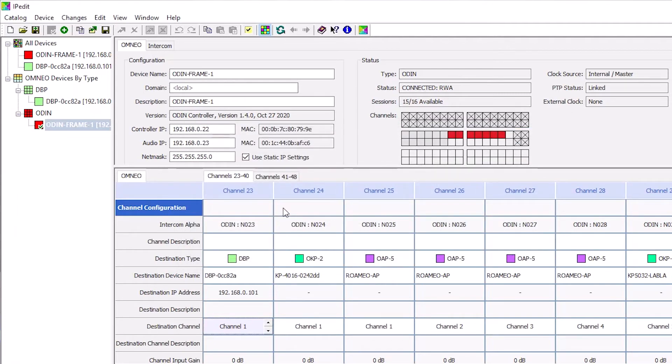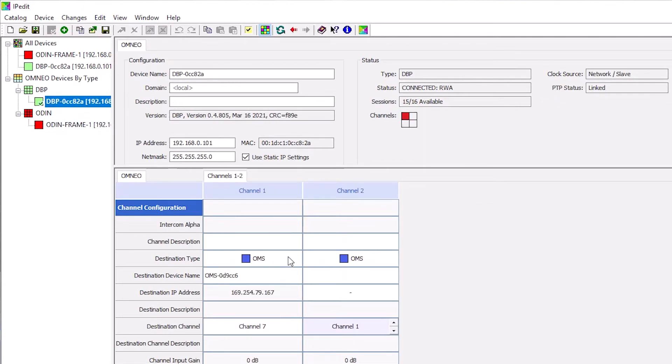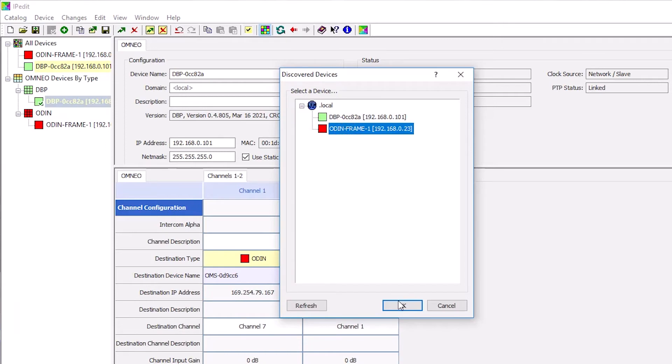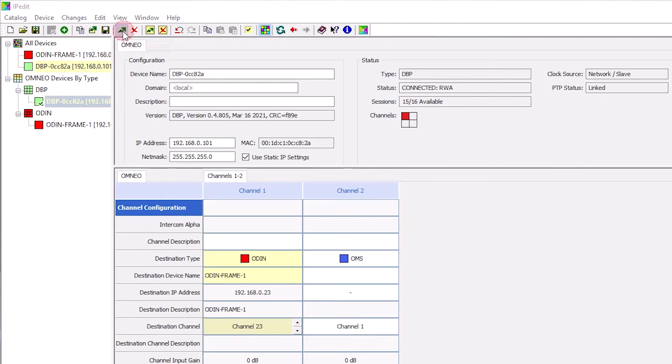Now we will configure an OMNEO channel for DBP using IP-Edit. Using the Channel Configuration pane, in the Destination Device Name field, click the Search button. The Discover Devices screen displays. Expand the tree to view the destination devices available. Select the desired device for the destination and click OK. The screen closes. Select the channel to which the device connects — in this example, I'm connecting to channel 23 on the ODIN. Send the changes to the DBP.